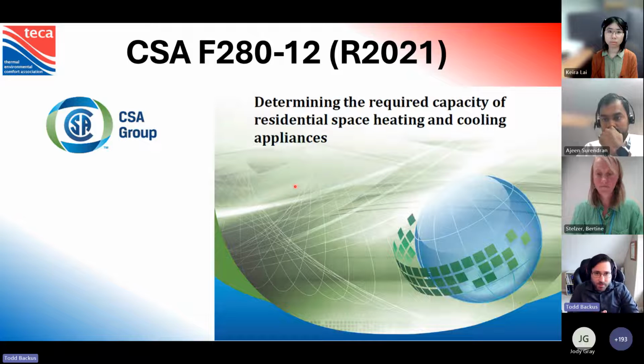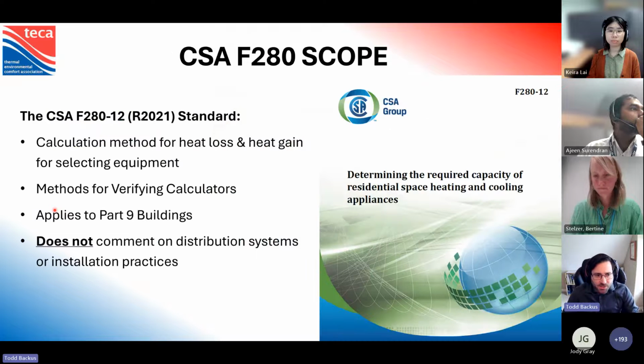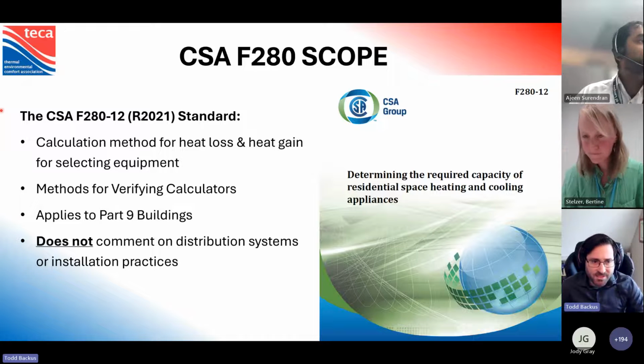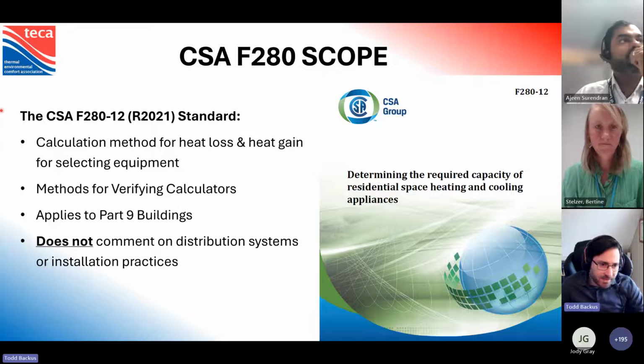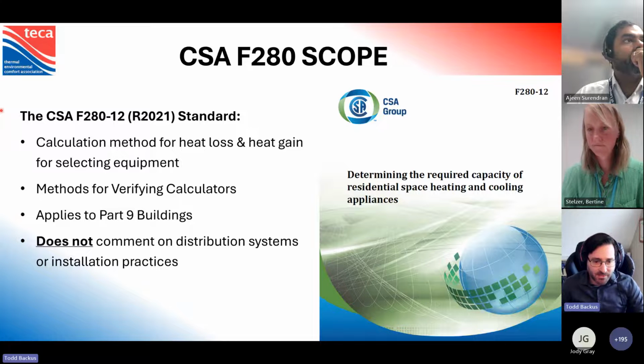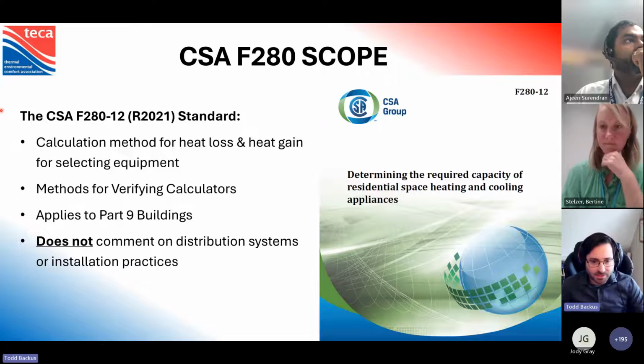So today we're going to talk about CSA F280-12, R2021, which is the full title of the current standard. And it is called Determining the Required Capacity of Residential Space Heating and Cooling Appliances. So what's covered in this standard is the calculation method for heat loss and heat gain with the intent of selecting equipment. It also provides methods for verifying the calculators, and it applies to Part 9 buildings. However, it does not comment on distribution systems or installation practices.